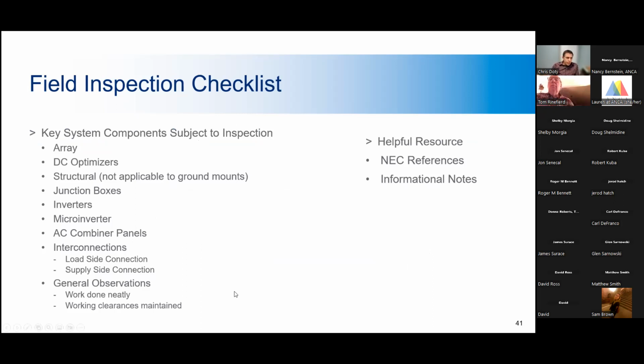So you would start at one end. Typically, you would start at the array and go down to the interconnection, or you could do it backwards. It doesn't matter how you do it, as long as you do it consistently. This will help you move through quickly each time and not make errors if you do it the same way each time. And so we're going to go through a basic run through of the basic items covered in the checklist from the array to the interconnection. So let's take a look at some of these components a little closer.